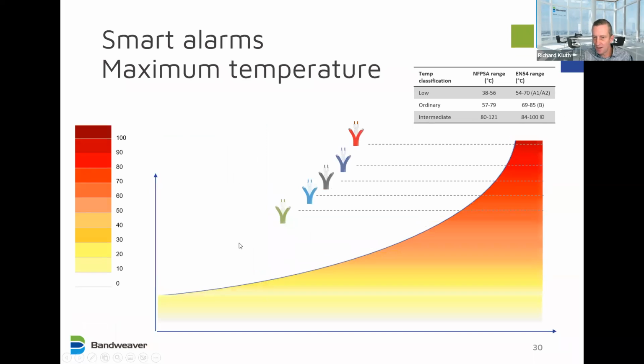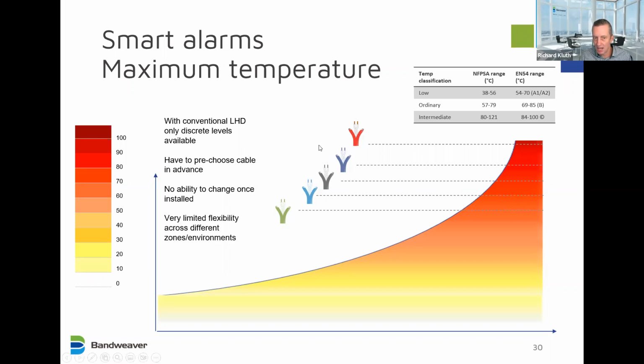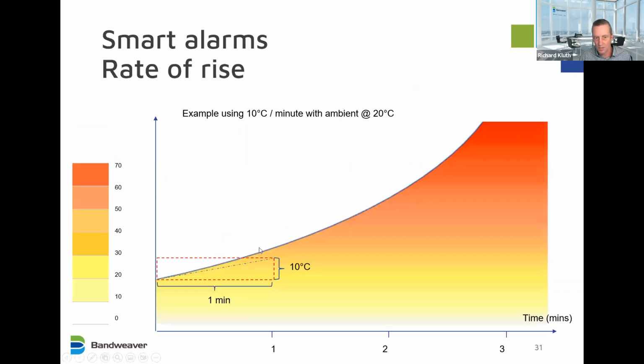So when we have conventional linear heat detection, copper-based systems, very often you have discrete levels depending on basically the material properties of the cable. So you have to pre-choose this cable in advance. Once the cable's in, you can't tweak it, you can't just change it in the software. You actually have to physically change the cable. And you've got very limited flexibility across different zones or environments. You'd have to actively change out the cable for the zone to change the level. So much less flexibility than with the fiber optic.